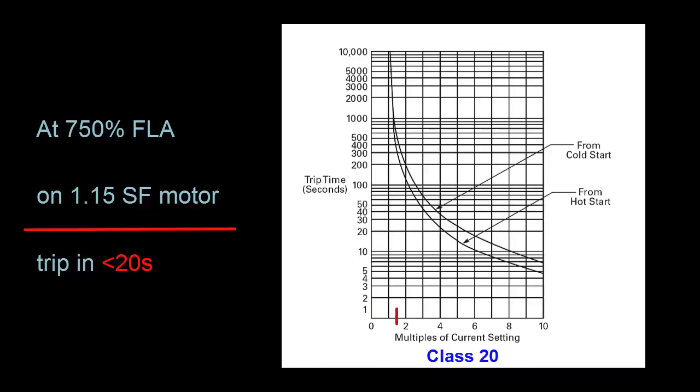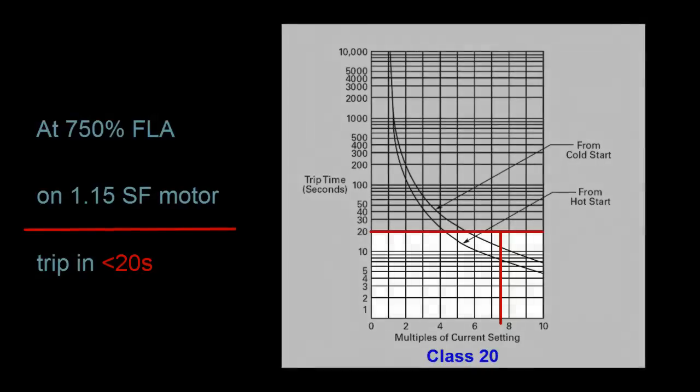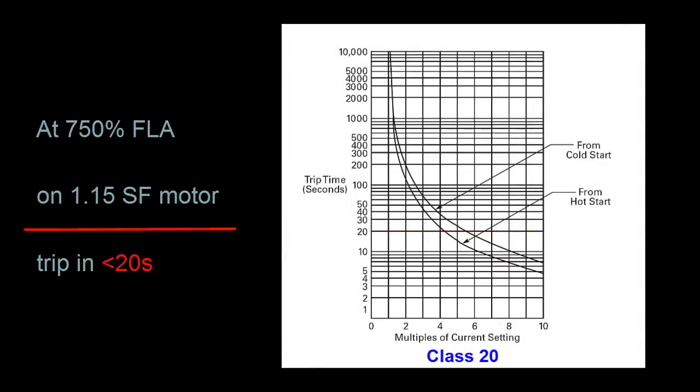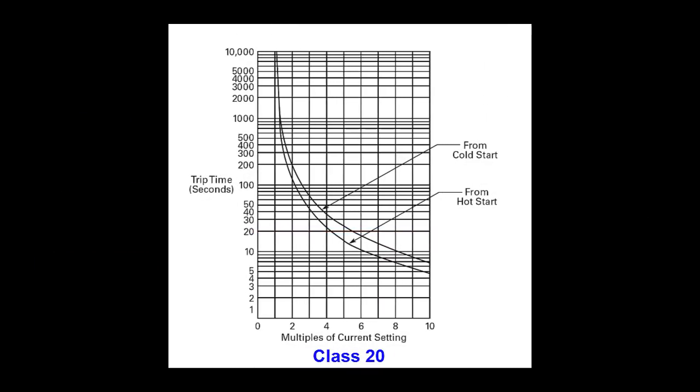So if we look at 7.5 times the FLA dial, we would expect to see it trip in less than 20 seconds, which it does. A trip class of 10 means that it would take less than 10 seconds to trip under those same conditions. The big takeaway from this is the lower the trip class, the less time it will take to trip.